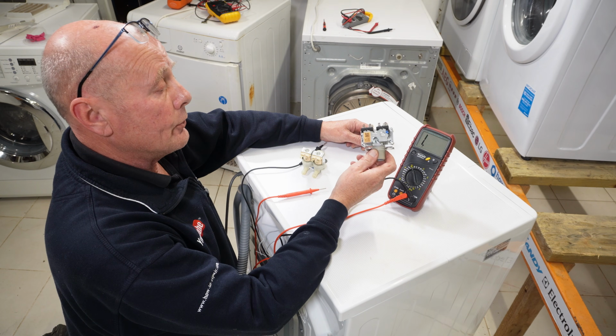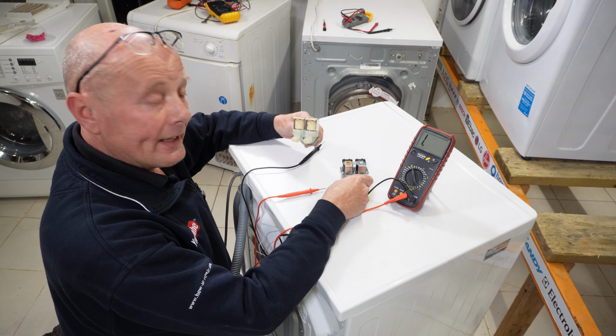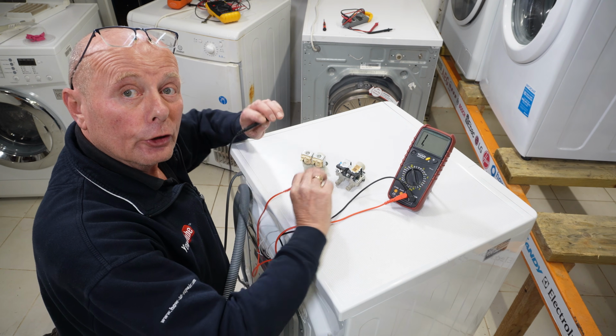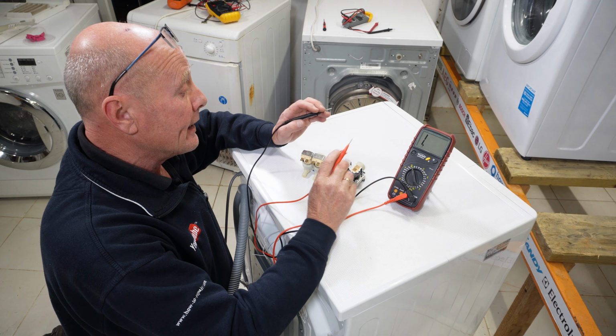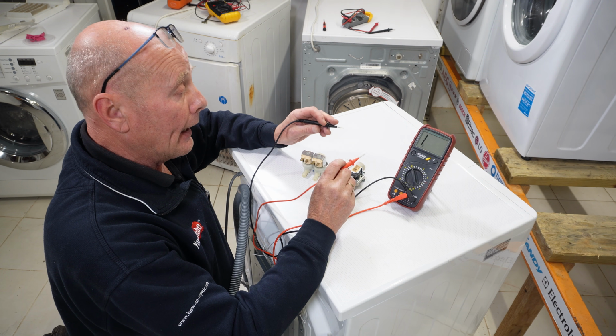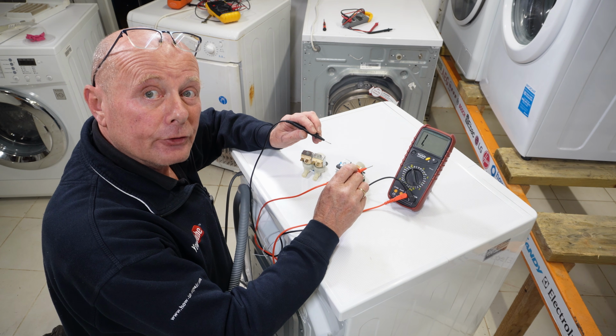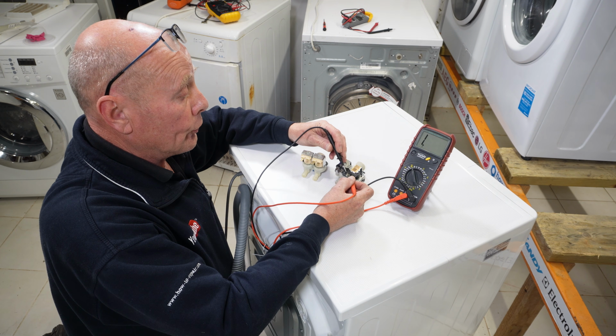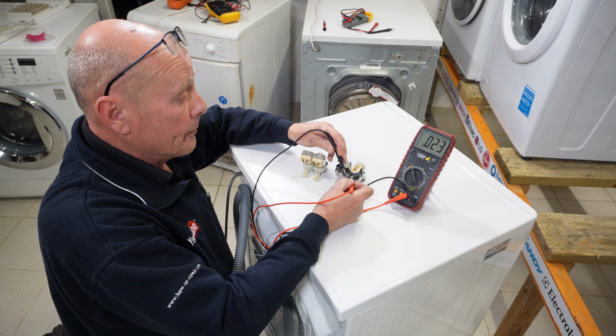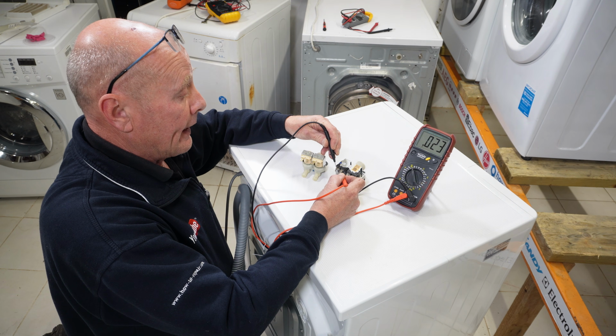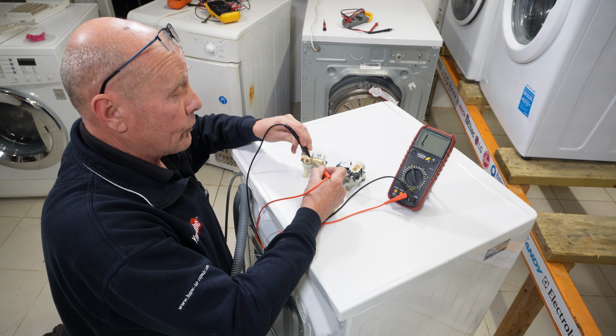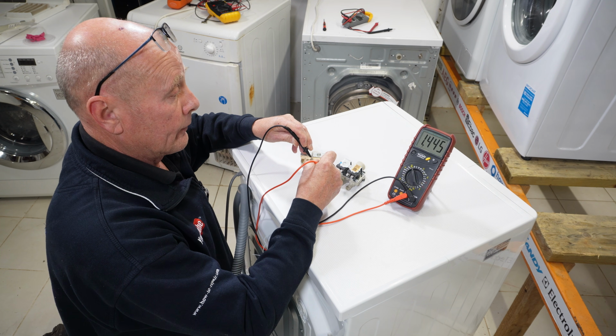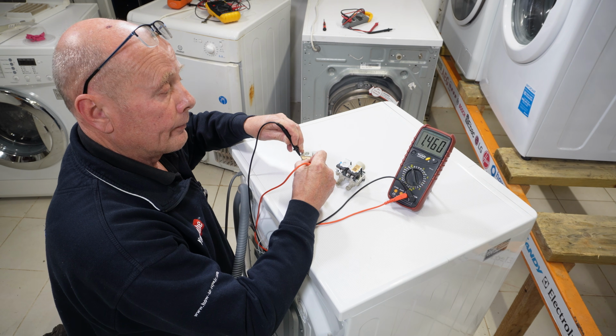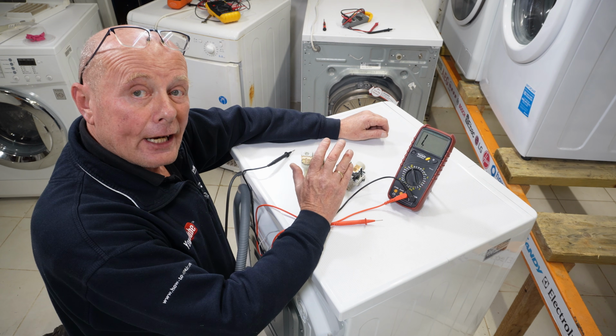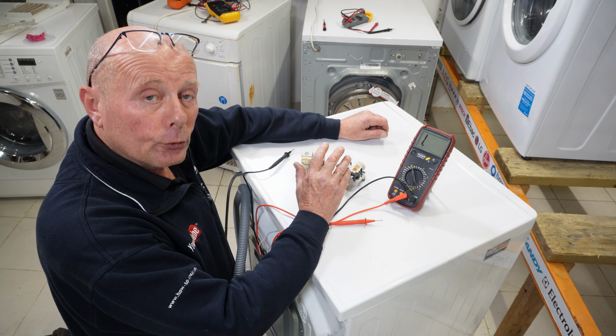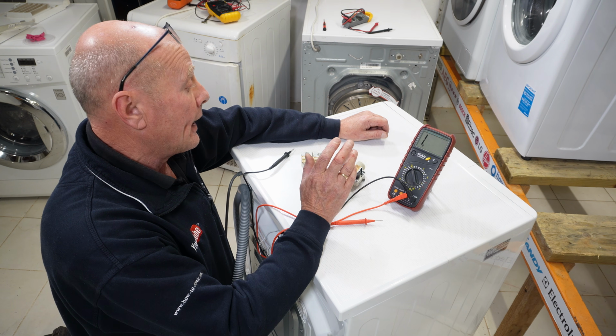Right, as I said, whether you have a DC water valve or an AC water valve, each of the coils will have a continuity in ohms reading depending on the size of the coil. I'm not going to go into depth on that because I have done a detailed video on it, but what you want to be checking is going across the coil, making sure that you've got continuity. As I said, all these valves are good, so this just gives you an indication of the reading. That's your first check, to check the coils. This would be a fault with the IE error code.